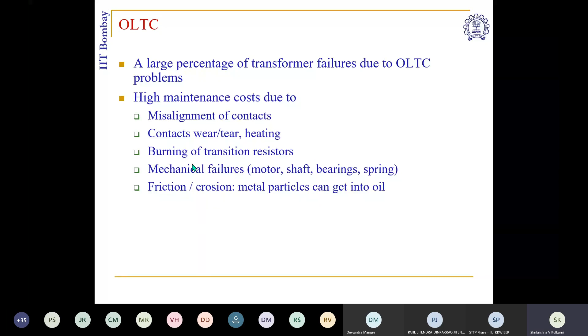So what are the parameters that can be monitored? Motor current. Where is the motor here? The motor is the one which basically changes automatically, it advances or retards the tap position, moves the moving contact. So this is done through a motorized operation. So motor currents are indicative of the condition of the drive mechanism.